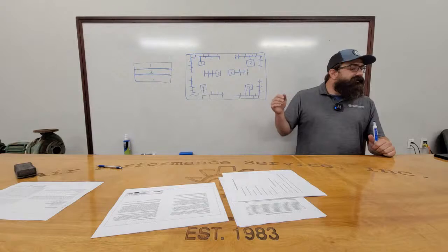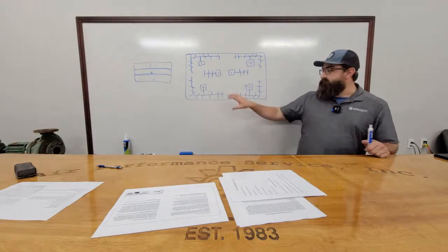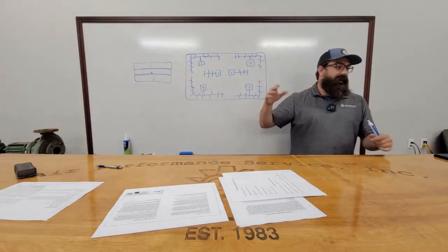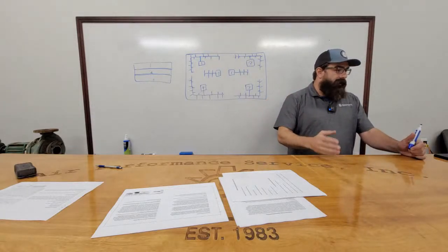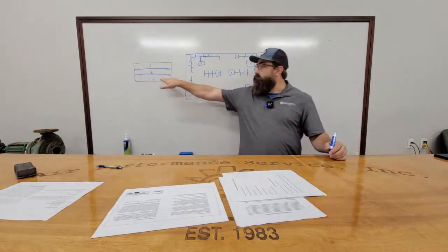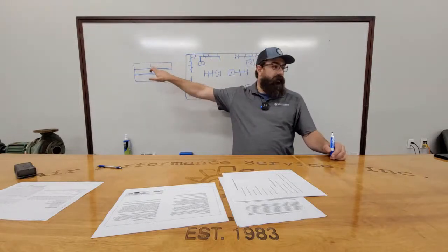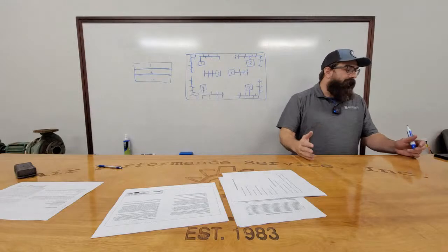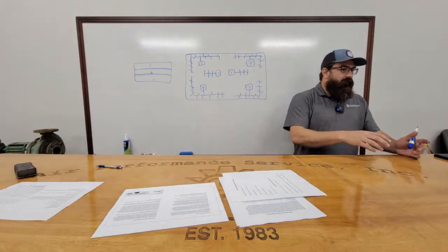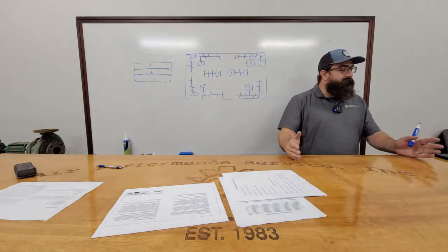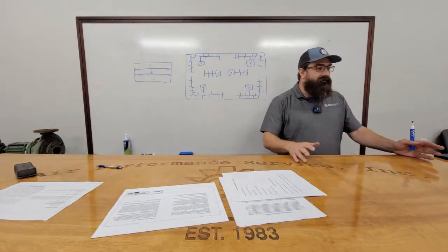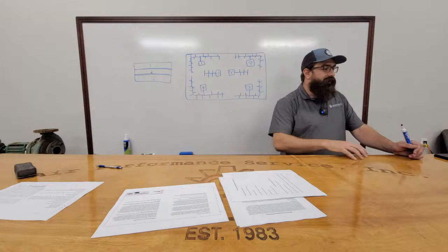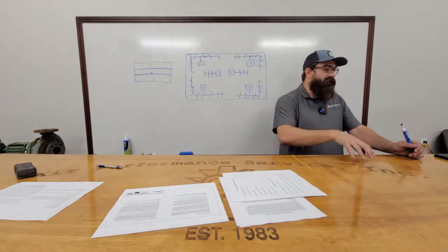we do 30 minutes per floor, and then we start these in groups when the building fires up. So we have an A, B, C, D group, and they're done by floor, and each floor may take an hour to start up based on how many groups we have for the floor. I don't remember exactly, but we have an energy meter that does graphing on the main for the building. We tried it a bunch of different ways, and whatever it is now is what we came up with was the best way to start everything.